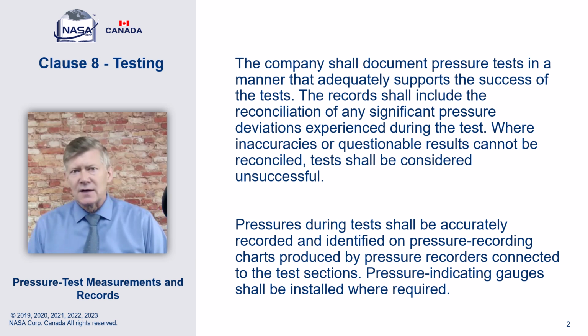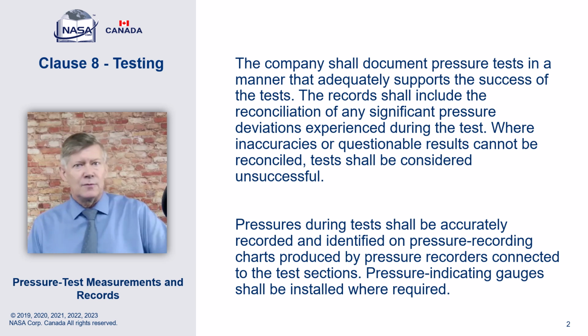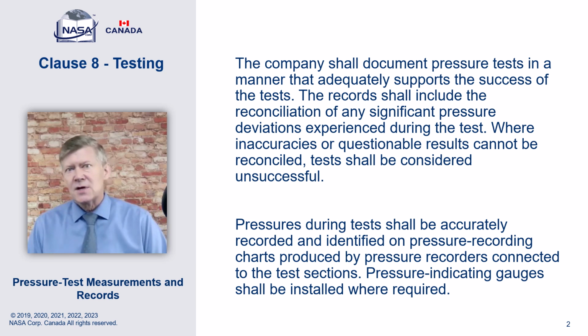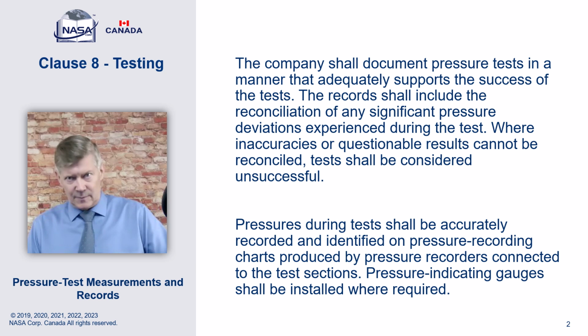Had a situation in an investigation a couple years ago where a pipe failed, and during the investigation we asked about testing, and they had said, oh yes, we did a service test just 3 weeks ago and it was fine, and we asked to see the records. We looked at the records, and from our perspective it was very clear. It showed that the pipe was leaking at that time.